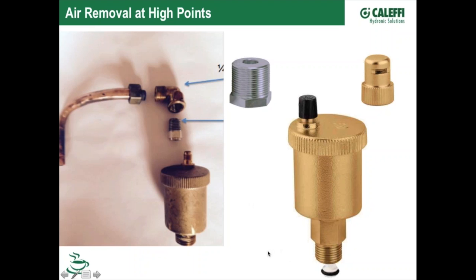So this we'll see a lot on boilers. You'll see this right on the heat exchanger, inside or outside the boiler. It's going to catch air that just rises up to that high point in the heat exchanger. You might see it up on an air handler at the high point in the building, in the ceiling, or if you've got a couple of riser pipes going up through the building, that's where this type of air elimination device would be applied.